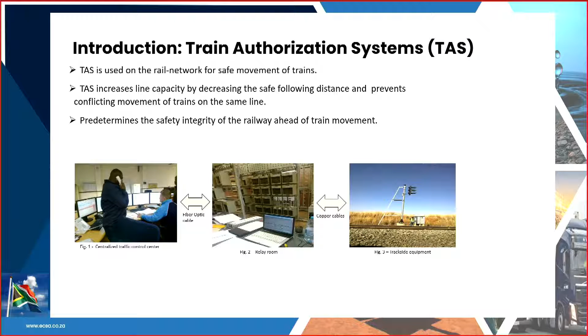Just to give you an idea of the cables we'll be studying - train authorization cables, which are low voltage copper cables. These are armored cables, buried underground at any level between 1 meter to 2 meters, to curb the escalating copper theft within South Africa, which is a very big problem. These cables carry a voltage of anything between 220 volts to 440 volts AC, and in terms of DC, 110 volts. Then there are various sizes in terms of cores, from 1 to 64 cores.